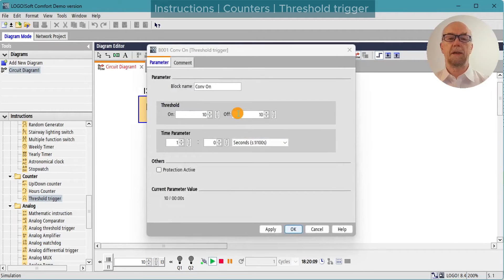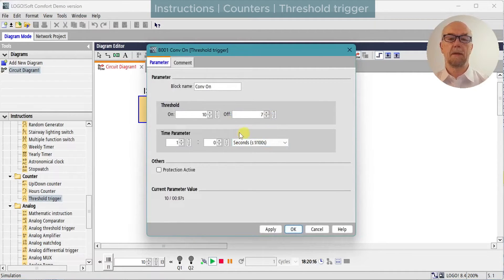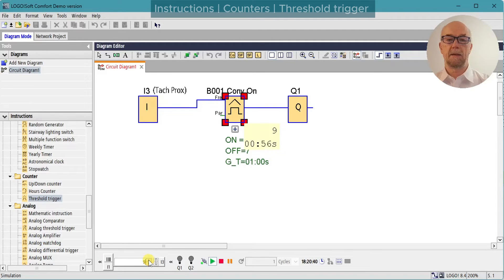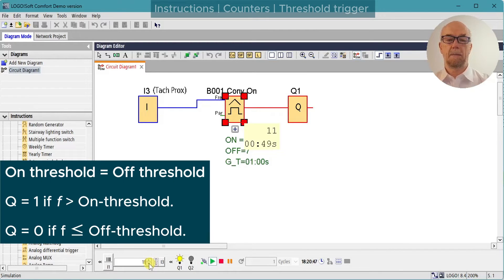We can modify the count and change the off threshold to a number less than the on threshold, so now it should turn on at 10 and off at 7. Starting at 10, we drop down to 5, then increment up: 6, 7, 8, 9, 10, 11 — it turns on. Back down: 10, 9, 8, 7 — it turns off. Notice there's a slight delay between when I change to 7 and the next timing period starting.